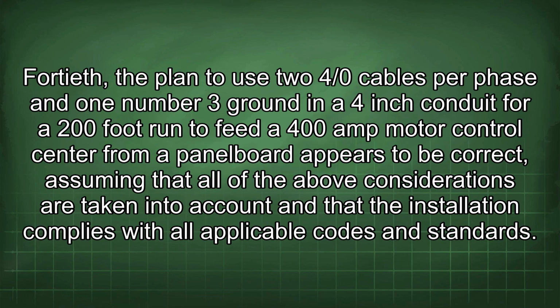40th, the plan to use 2 4/0 cables per phase and 1 number 3 ground in a 4-inch conduit for a 200-foot run to feed a 400-amp motor control center from a panel board appears to be correct, assuming that all of the above considerations are taken into account and that the installation complies with all applicable codes and standards.